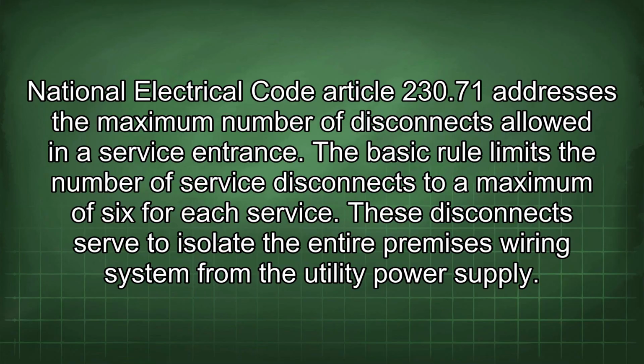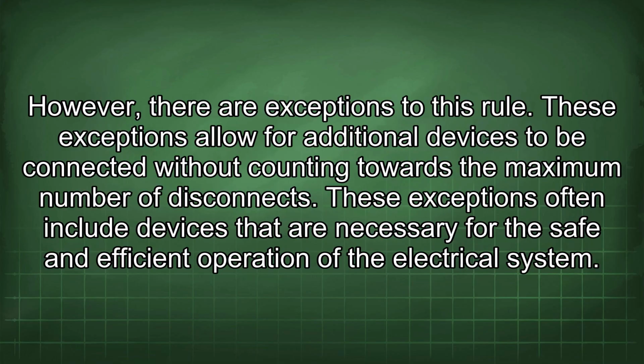National Electrical Code Article 230.71 addresses the maximum number of disconnects allowed in a service entrance. The basic rule limits the number of service disconnects to a maximum of 6 for each service. These disconnects serve to isolate the entire premises wiring system from the utility power supply. However, there are exceptions to this rule.